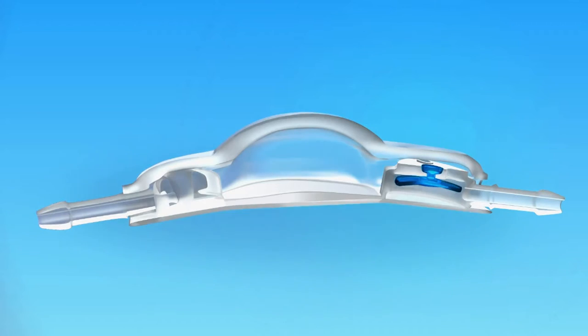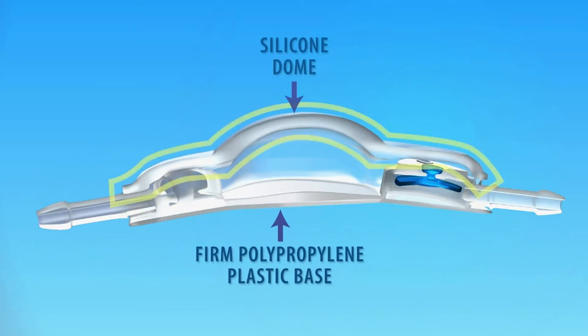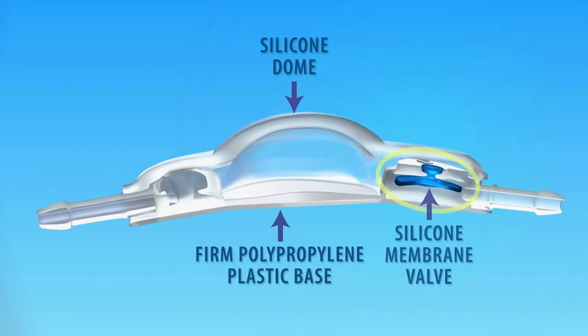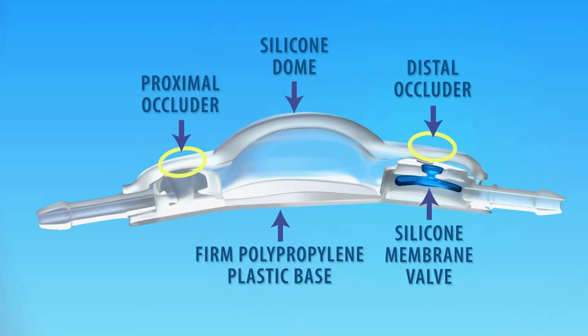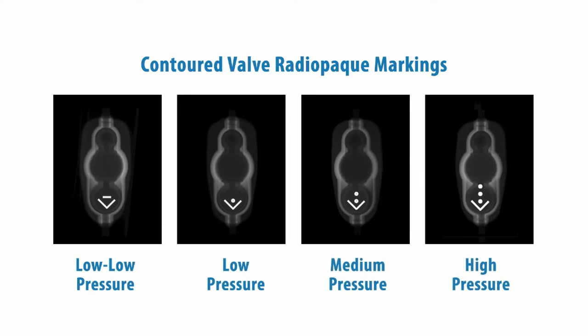The Medtronic contoured valve consists of a polypropylene base, a silicone dome, and a silicone membrane valve. The contoured valve also has proximal and distal occluders for selective flushing. Additionally, the contoured valve has radiopaque markings.